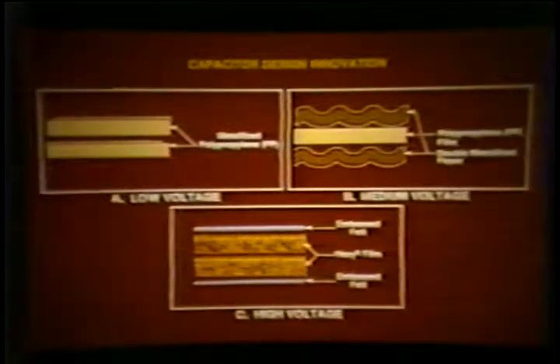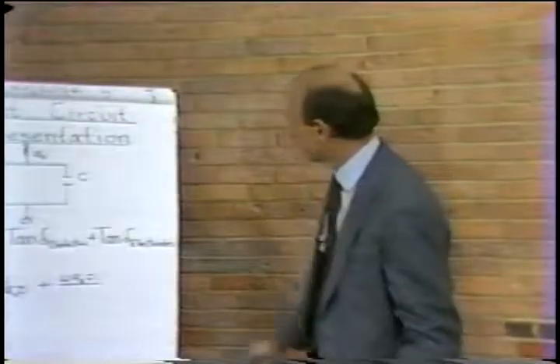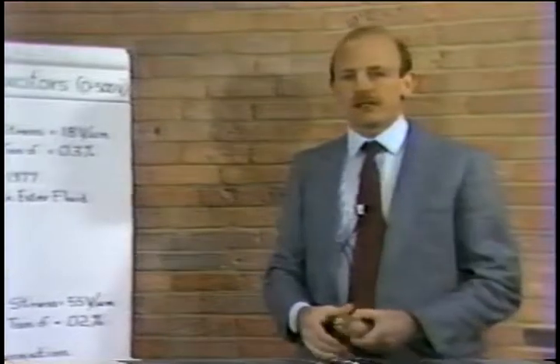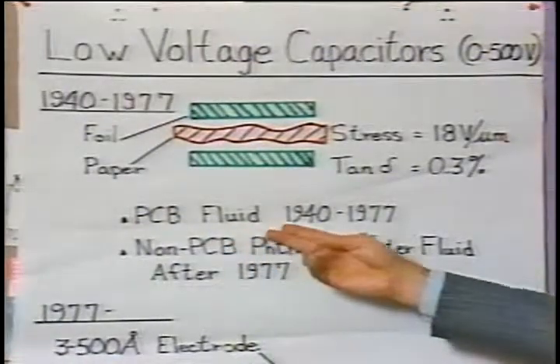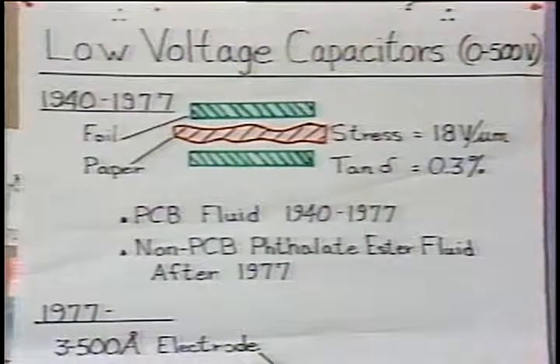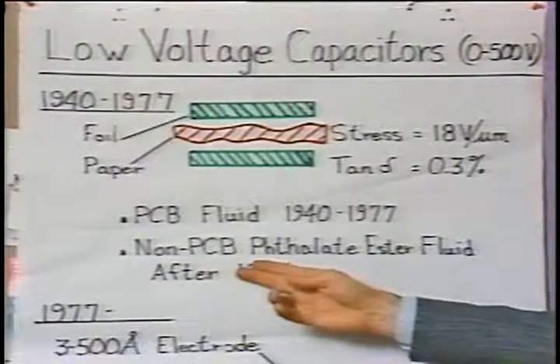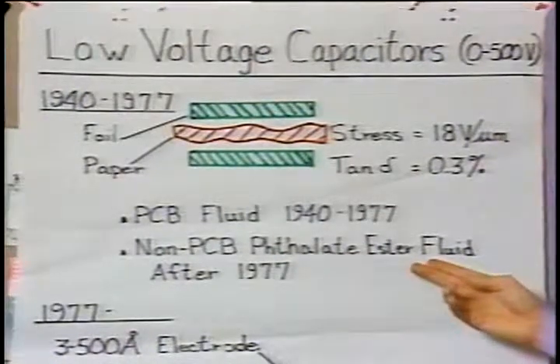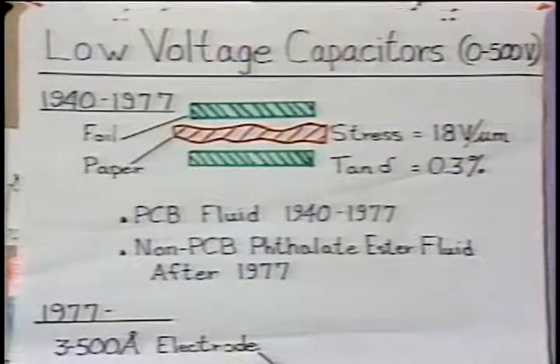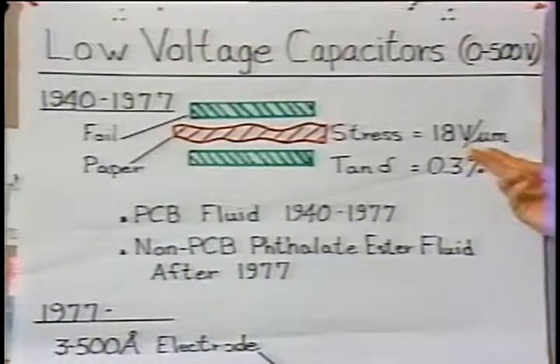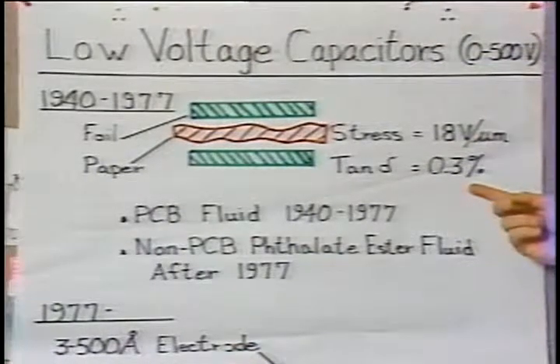Now let's take a close look at each of these designs, starting with the low voltage area. Historically, in this voltage region, the capacitors have always been constructed of paper dielectric and aluminum foil electrodes. They've been impregnated with a PCB, or polychlorinated biphenyl fluid. This has served us well in the time period from 1940 through 1977. For environmental reasons, the fluid was then changed to a non-PCB liquid. For example, the phthalate esters. A typical example would be dioctyl phthalate. The stress that's applied to the paper is approximately 18 volts per micron. The dissipation factor is 0.3%.